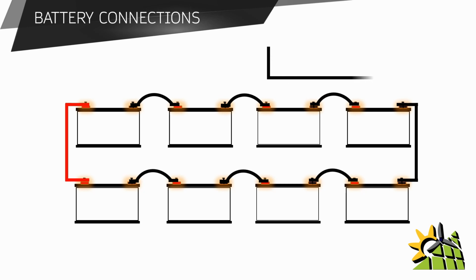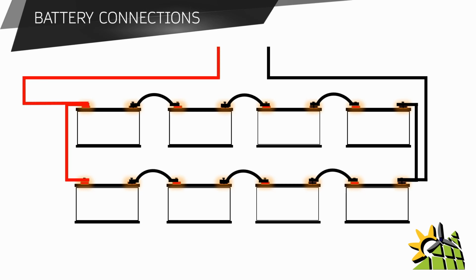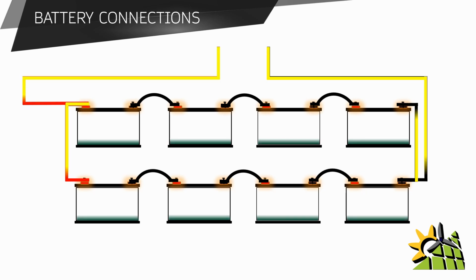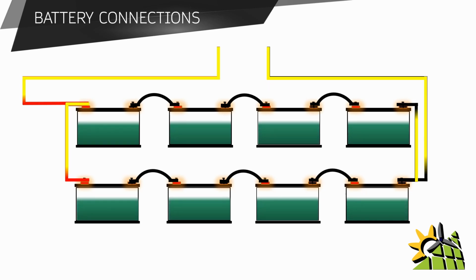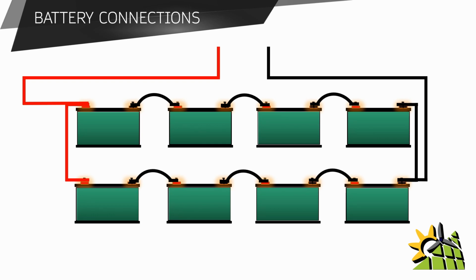The negative cable from the inverter or the battery charger should be connected to the negative terminal of the last battery bank, and the positive cable from the inverter or the battery charger should then be connected to the battery bank's positive pole. By connecting the batteries in this manner, all the batteries will receive equal charge and all the batteries will be fully charged.